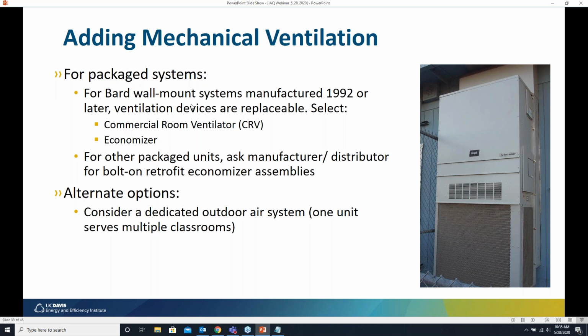For any Bard wall mount system manufactured after 1992, the ventilation devices are replaceable. You can see in this photo where the outdoor air comes into this Bard system. This essentially is a slot, and the ventilation systems they sell for these HVAC systems are interchangeable. If you have a non-compliant system that can't be adjusted, you can buy just the ventilation device and swap it. So that's one fairly practical way to increase ventilation in wall mount systems where, for whatever reason, the original ventilation device may not be capable.